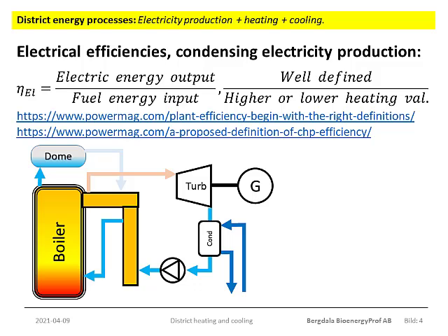So for the practical reasons just mentioned, the limit of the electricity efficiency based on the lower heating value will be around 40, 45, maybe 50%. Since there is only one product, electricity, the total efficiency will be the same as the electrical efficiency. So based on the higher heating value, the corresponding numbers would be reduced by some 5, 10 or maybe a bit more percent? Anyway, more than half the fuel energy is simply lost in the cooling water.